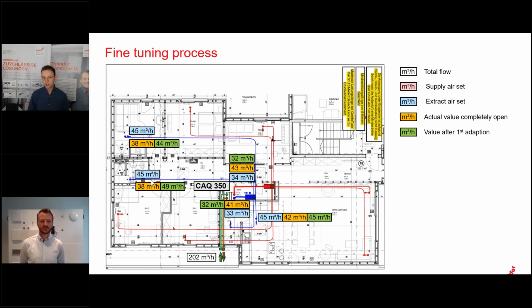You will get a feeling for this. But at the end, the volume flows don't need to fit 100%. Here we are already quite close. You could just adapt the one with 49 cubic meters, and then you can check what the other valves are doing. The goal should be at the end that the last valve, the one with the highest system pressure drop, is completely open, so that the fan needs to bring the least achievable pressure rise for that system and therefore works in the most efficient way. This is the way we recommend to adjust the system. I hope that was clear for you. That's it from my side for the moment. Now Tobias will show you how you can do these measurements.